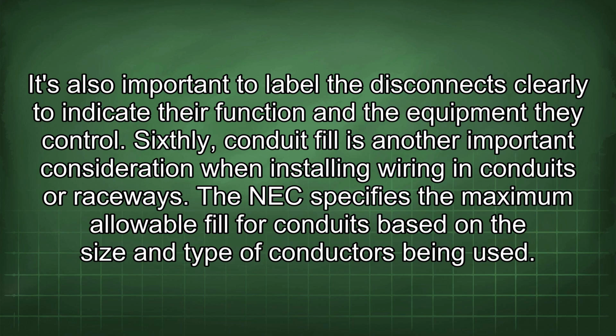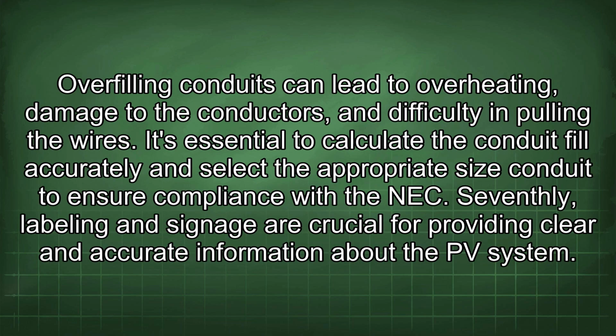Sixthly, conduit fill is another important consideration when installing wiring in conduits or raceways. The NEC specifies the maximum allowable fill for conduits based on the size and type of conductors being used. Overfilling conduits can lead to overheating, damage to the conductors, and difficulty in pulling the wires. It's essential to calculate the conduit fill accurately and select the appropriate size conduit to ensure compliance with the NEC. Seventhly, labeling and signage are crucial for providing clear and accurate information about the PV system.